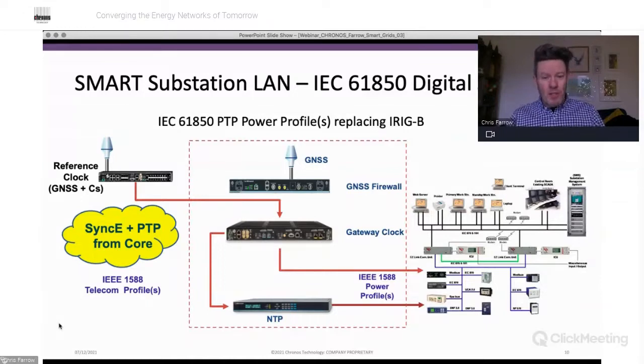Our local substation, shown in the middle and right-hand portion of this slide, is designated by these clock entities, these functional entities, where we still have local satellite time receivers. So we can get local time from satellite receivers if our reference clock in the network has an issue or our network link fails. We're using a GNSS firewall, which looks in depth into the data within those satellite signals to make sure they're not spoofed, and that no attacker is trying to steer the time in our substation to cause faults.